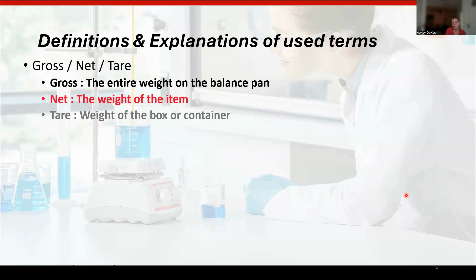No problem. So gross, net, tare: you may hear these words and not understand them fully. Gross is the complete weight of the entirety of what's placed on the balance pan. The net is the weight of just the item, and the tare is the weight of just the box or the container. That's important to know before you choose a balance, because you have to factor in the weight of that container, as it will take up some of the maximum capacity of the balance.